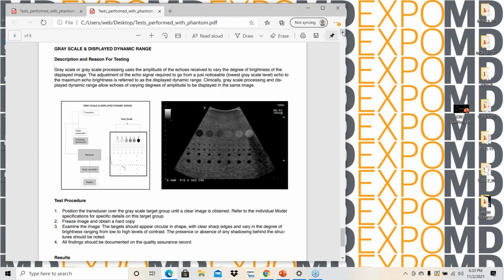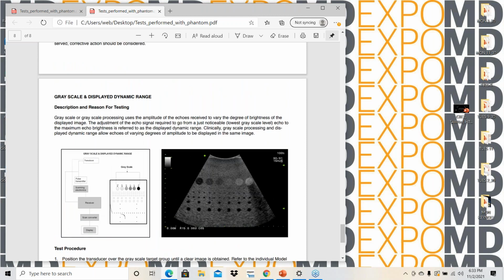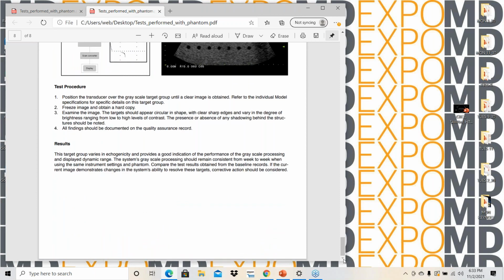That's really what I have. Like I said, I'll send it to you. It's all in English. I don't need to read it to you. If it was in physicist language, then there'd be problems, but it's not. So that's the end of the thing. I'm just showing you the tests that we do. We do them on every PM and any call I'm going to that says image quality in the title. If you do not establish a baseline the first time you work on the system, an image quality issue is really difficult to track down because they can't define it, right? It's subjective. Ultrasound is very subjective.